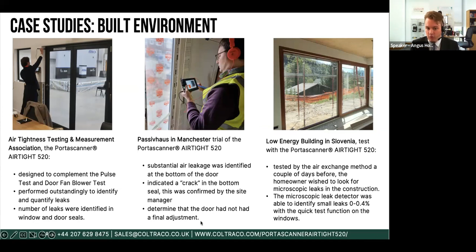However, when we tested the door, we found a number of different leak sites in a couple of the corners at the top, but particularly we found really quite substantial leakage at the bottom of the door. And this went across the full extent of that, which indicated to us that there was a crack. When we went back and told the site manager about these results, he confirmed to us that, in fact, the door had only just been put in and had not yet received any final adjustments. And based on the information that we provided them, they knew where to start with that already. Thank you. Next slide, please.